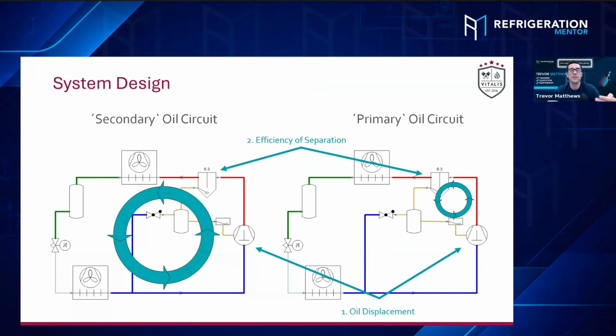And these are all the things that we need to look at as technicians when we're out there servicing. Don't just go adding oil and removing oil. There are situations we'll talk about where you might have to do that to figure out what the problem is. But if you put in 3 or 4 gallons, you need to take 3 or 4 gallons out, especially if it's been running for years. Like startup, this is where everything should be taken care of.